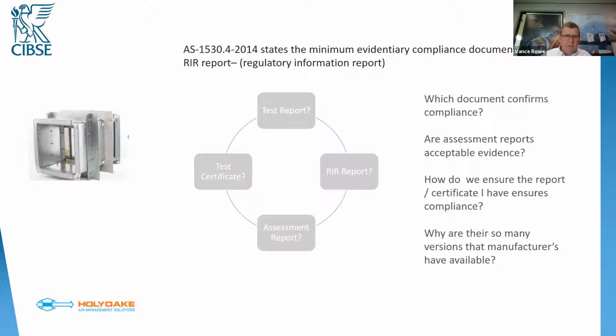And of course, the industry wouldn't be able to decipher the information in all of those reports. In fact, if we tested in this particular type of concrete or Hebel panel, nobody else could use that data out in the industry based on that particular test report. So what we do is we take that range of tests, we work together with the RTA, and then they write us what's called a full assessment report. That covers all of that test data, all of those different wall and floor substrates, so that we've got all of that information in a way that people can decipher it, read it and understand it, all in the one place. We then condense that report down into an RIR report, or some RTAs will now call that a short form assessment report, and that meets the requirements listed in AS 1530.4 as the minimum evidentiary requirements for fire testing. And that's kind of how it works.